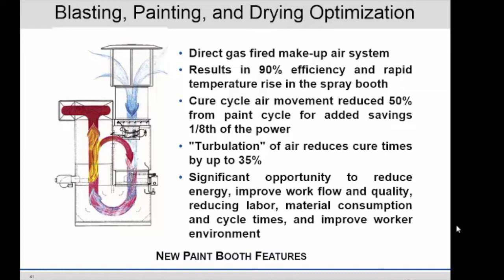Right here, it's showing you, typically, this is a direct gas-fired airflow diagram for a painting booth that you would buy from a commercial painting supplier, okay? And you get very high efficiency with the direct gas-fired, okay, 90%. You reduce the airflow tremendously. These also are recirculating 80% of the air. So instead of heating and cooling 100% of this airflow, you're only doing 20% when you're not painting. Some of the people that do this painting don't want you to do recirc when they're painting. But you could do it when they're not painting, when they're curing or when the thing's just sitting there.